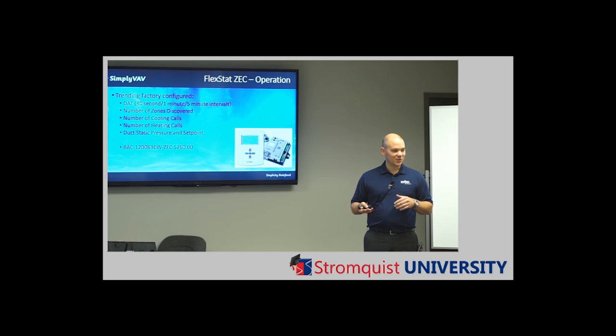Pressure dependent systems also, because you have no guarantee of how much airflow is going through, you're not getting enough dehumidification generally through your equipment. So pressure independent VAV provides better comfort, better ventilation, and better performance overall in your system.